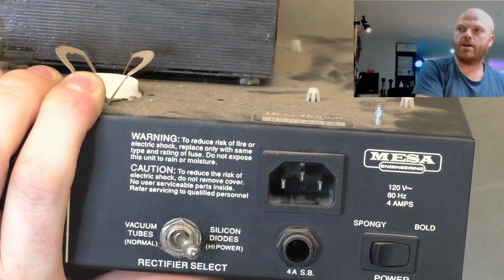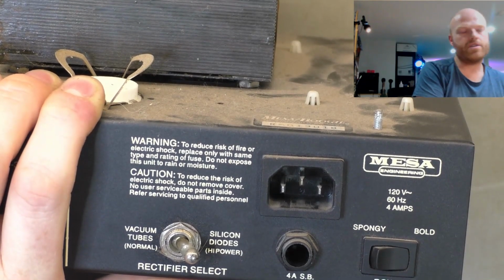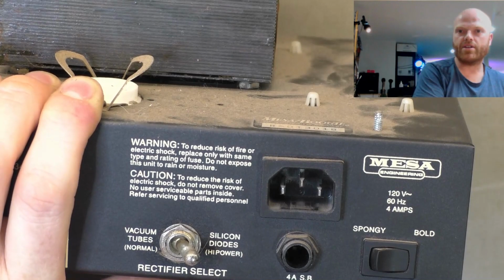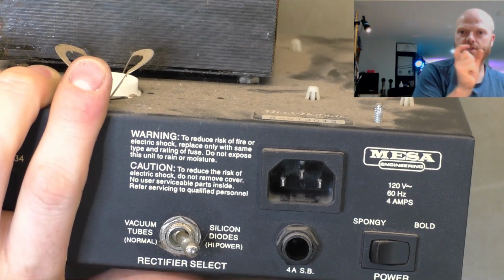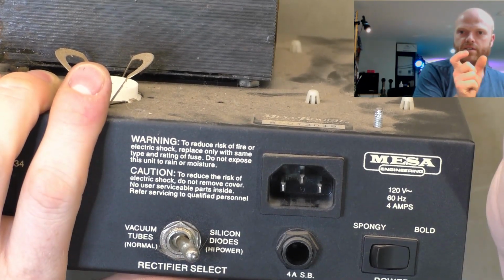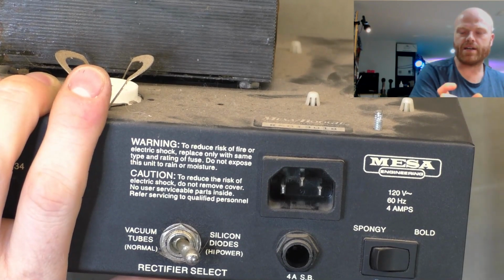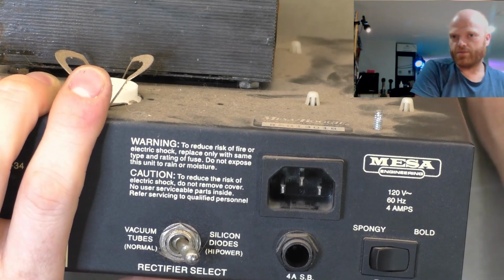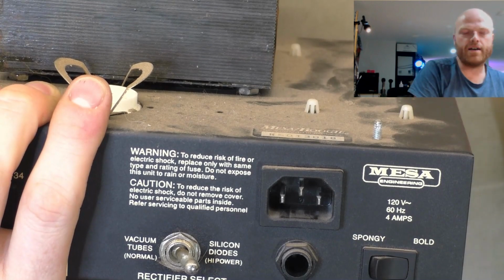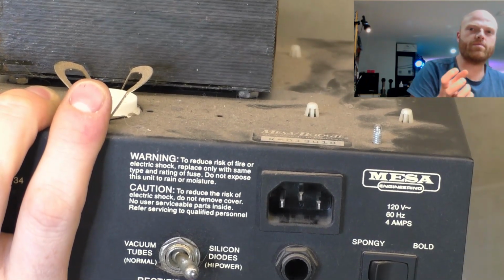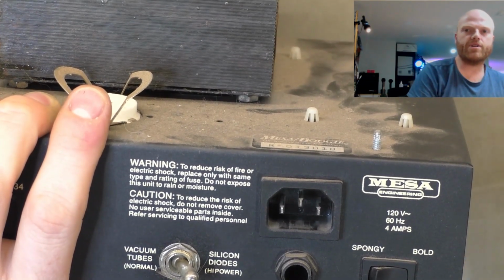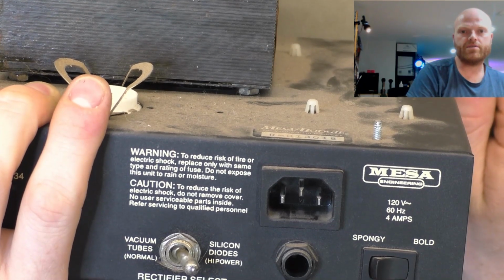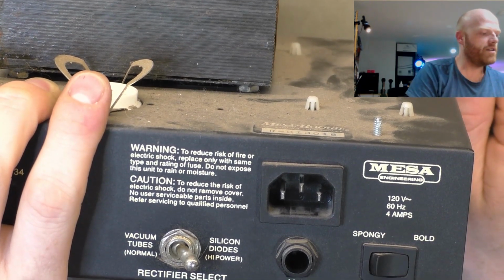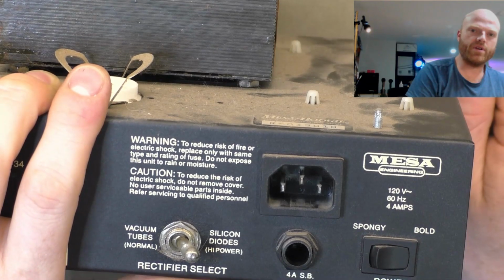If you look at switch mode power supplies these days, you've got these monster power supplies in like 1000 watt bass amps, and the transformer's not much bigger footprint than a packet of Tic Tacs. That's because it's switching at like 100 kilohertz or higher. The core size is proportional to the power as well as the frequency that it's transforming. The higher the frequency, the smaller the core you can have.